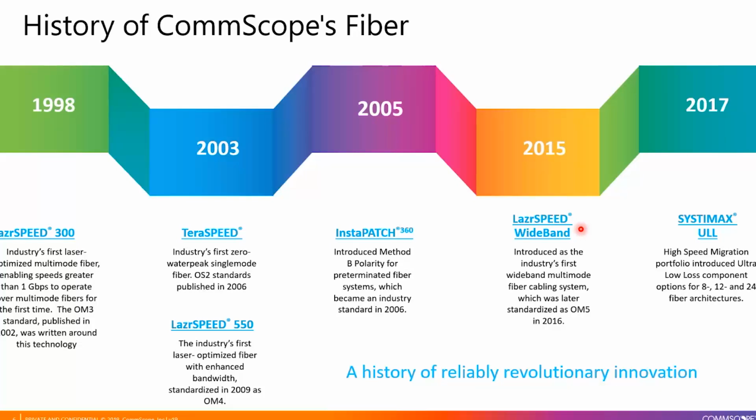But with the SWDM technology, the short wave division multiplexing technology, it drives four wavelengths on a single fiber. Nowadays you are getting fiber optics which can support four wavelengths on a single port itself. To support that, we needed a better fiber cable on multimode. That is why we call it a wideband multimode fiber cable. That became a standard as OM5 now. So this wideband multimode fiber cable will play a major role inside the data centers.